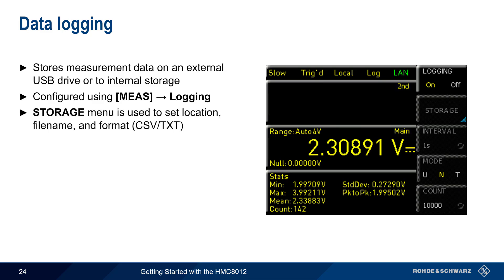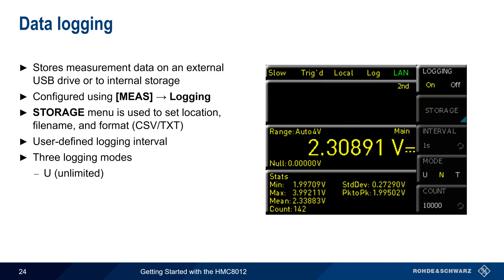The HMC 8012 can store or log measurement data to either an external USB drive or to its internal storage. This is configured by pressing the measure hard key and then selecting logging. The storage menu is where the logging location, file name, and format are specified, and the logging interval, or time between recorded values, is user definable. There are three logging modes: unlimited mode runs until the storage medium is full or logging is manually turned off; logging can also be configured for a defined number of samples; or it can run for a user-defined period of time entered in units of seconds.